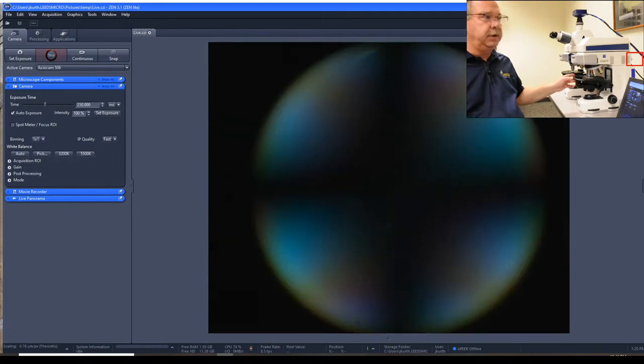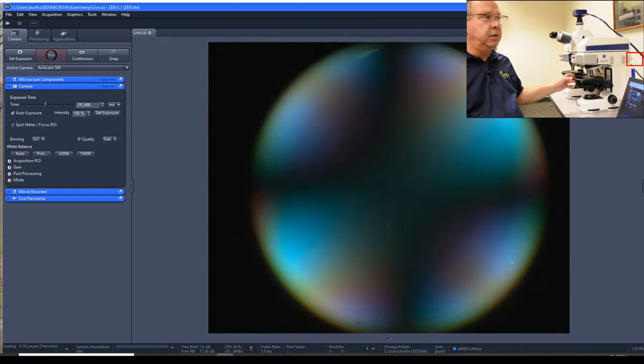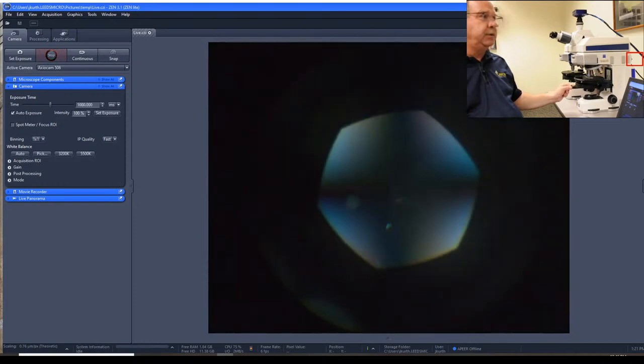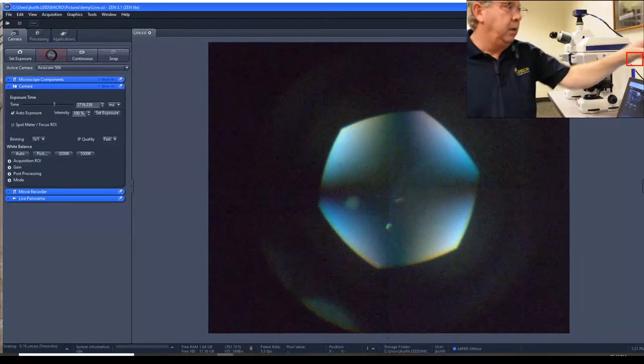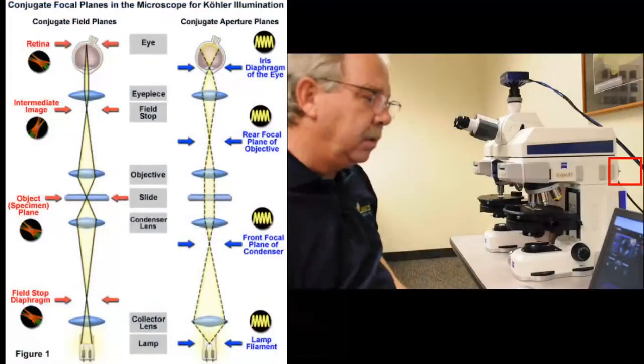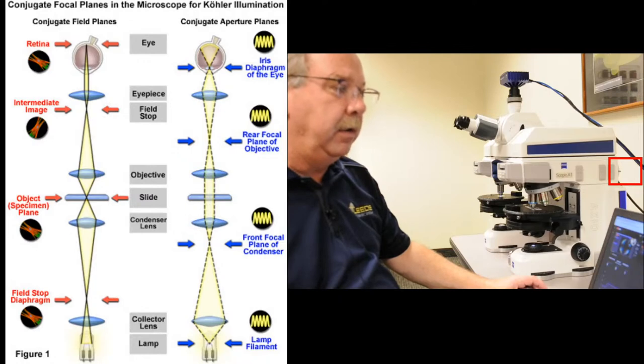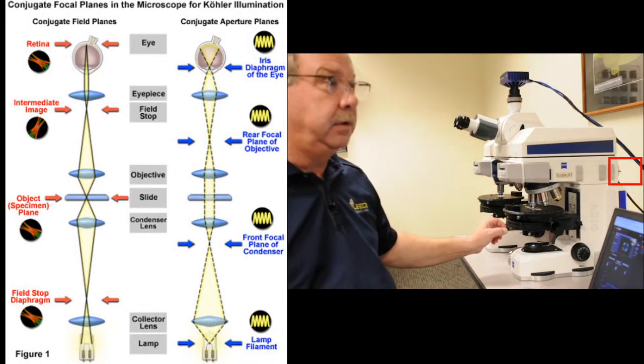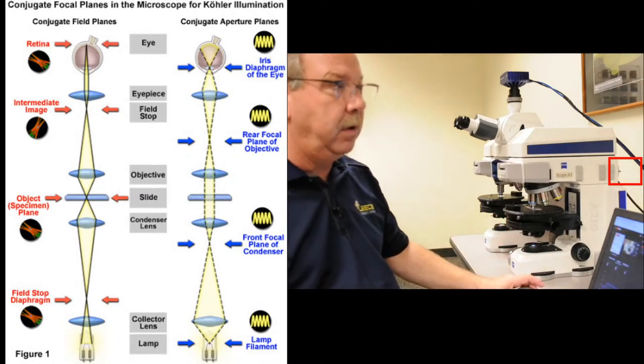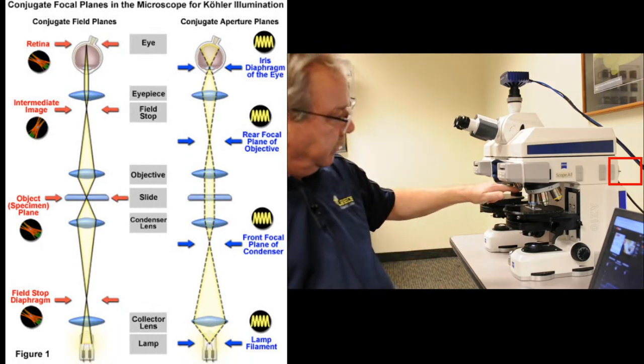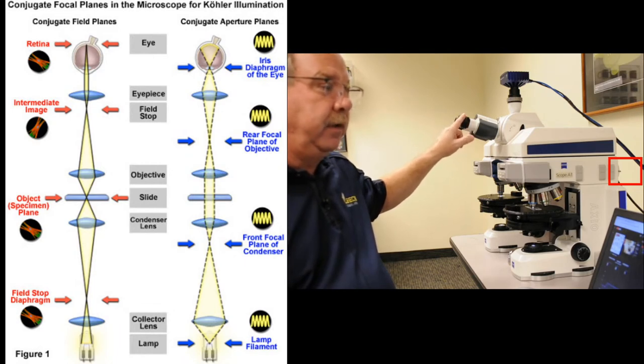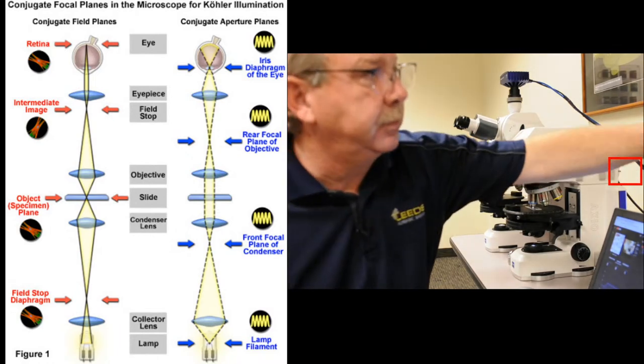If I'm correct in how I taught you all of this, as I close down the aperture diaphragm, you see the aperture diaphragm. Why do I see that? Because going back to the optical diagram, the conjugate planes include one in the condenser located at the aperture plane — which is why I see it. You can see how important it is to have that aperture diaphragm all the way open. The aperture plane is in focus, the rear focal plane of the objective is in focus, and we aren't seeing the one that would normally form at the front of our eye because we've inserted a different optical system to allow us to see the interference figure.